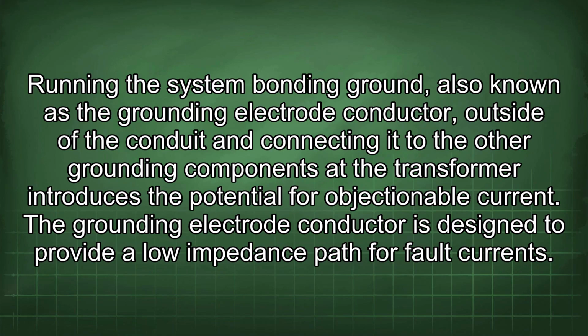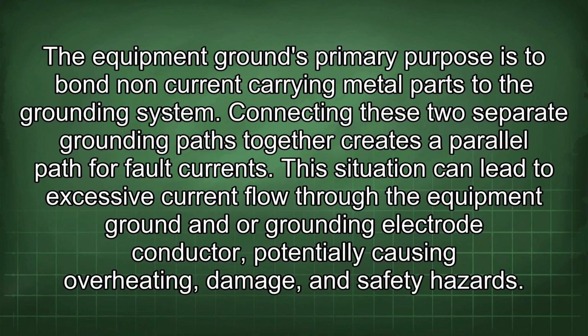Running the system bonding ground, also known as the grounding electrode conductor, outside of the conduit and connecting it to the other grounding components at the transformer introduces the potential for objectionable current. The grounding electrode conductor is designed to provide a low impedance path for fault currents. The equipment ground's primary purpose is to bond non-current carrying metal parts to the grounding system. Connecting these two separate grounding paths together creates a parallel path for fault currents.